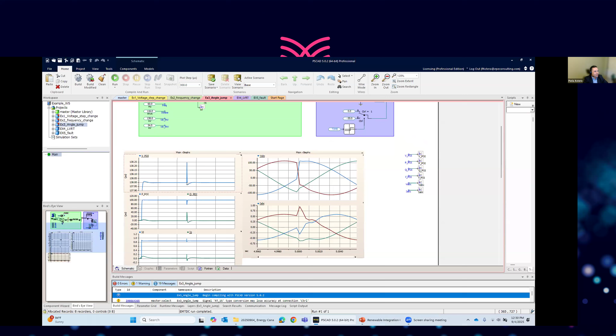So it goes as expected. There is some disturbance here because the angle is changed. Again, the PLL needs to find the lock to the new phase, but it's going well. And there is some frequency measurement error that happens in reality as well, because it depends on the method that you use to measure the frequency. That can cause problems in real-world cases, where an angle jump could, for example, create a frequency change that activates protection or other devices. The real frequency is not changing, but the measurement method shows that. It's something that we can see in the EMT simulation, for example, and we cannot see in the RMS simulation.